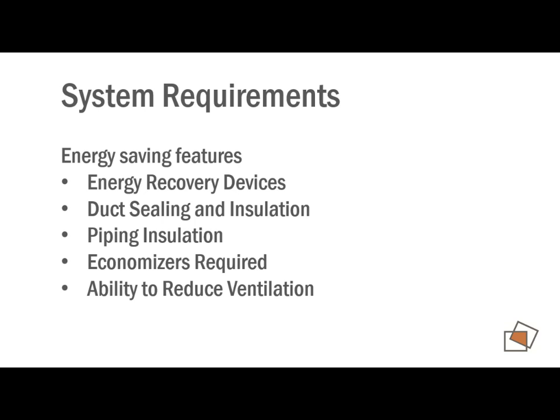So it's great technology, really great if you have rooftop units because it's easy to integrate. As long as the contractors get it set up right, you don't bring just fresh air in all through the summertime, because there are adjustments on these things and they need to be calibrated. But anyway, the 2012 Energy Code requires economizers for equipment that's 3 tons and up. So it's not really big, a 3-ton furnace isn't a very big furnace.